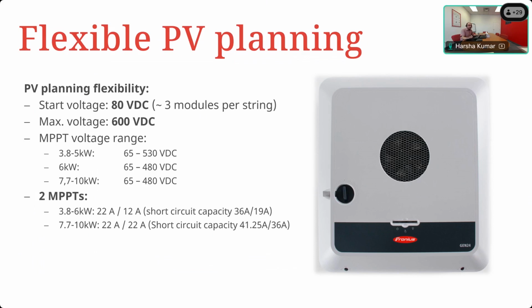Okay, so which means that now you can even use the higher powered modules, which tend to have much greater short circuit currents than the earlier ones, when the Primo or the Symo were launched. Now, similarly, on MPPT2 of the smaller power classes, the usable current is 12 amperes and the short circuit capacity is 19 amperes. For the larger power classes, the power capacity is equally shared across both MPPTs. So it is not 2/3 and 1/3 like the smaller power classes.